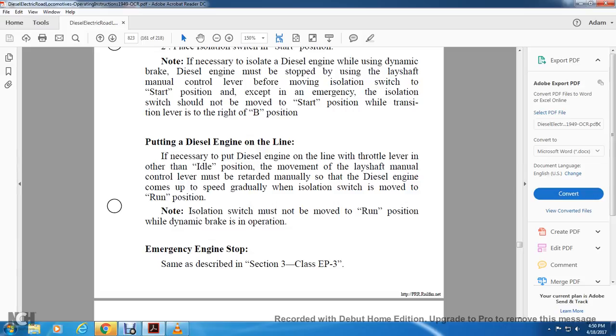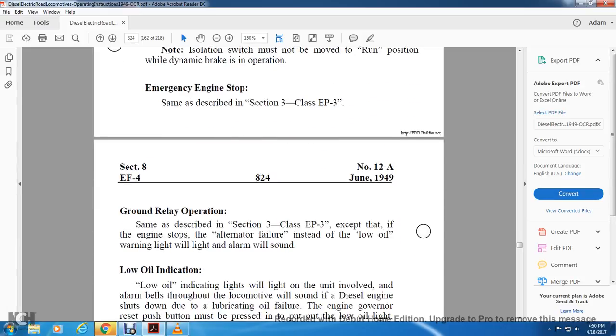Emergency engine stop is the same as described in Section 3, Class EP3. Ground relay operation is the same as described in Section 3, Class EP3, except that if the engine stops, the alternator failure light will light instead of the low oil warning light, and an alarm will sound.